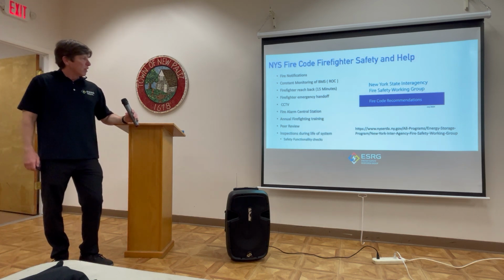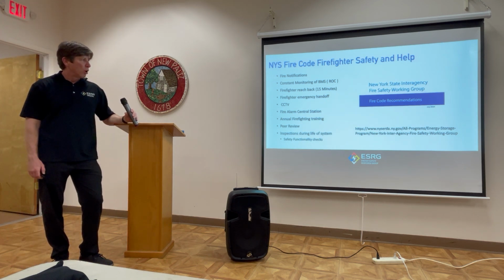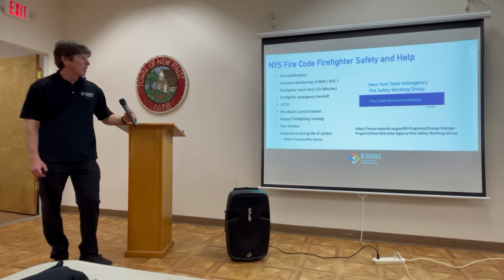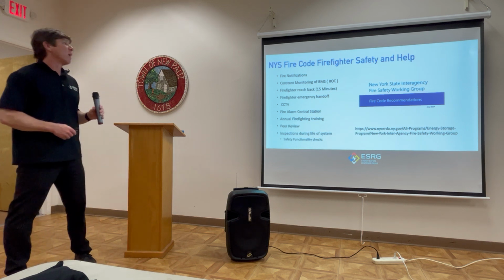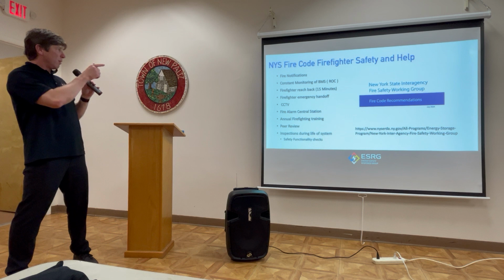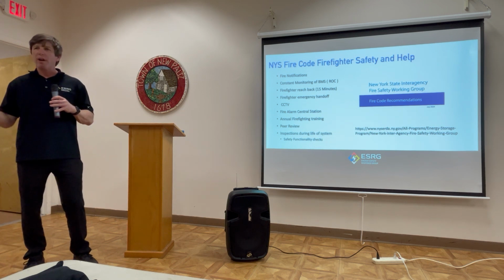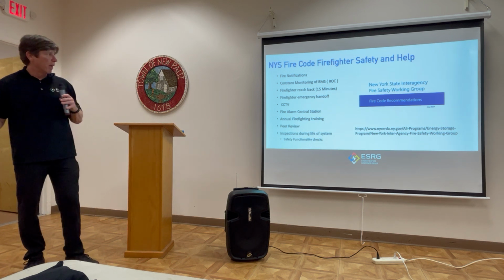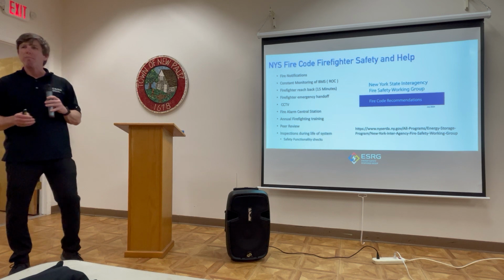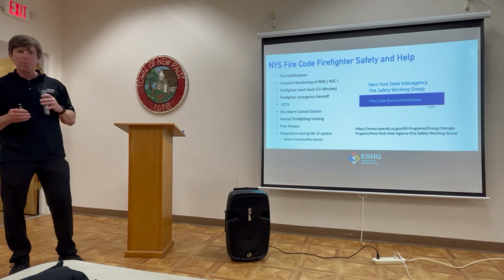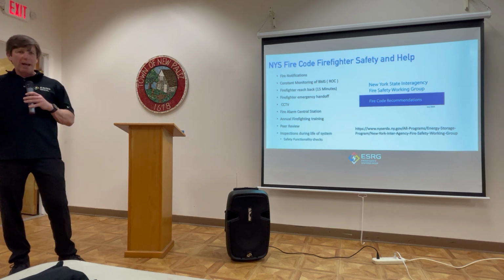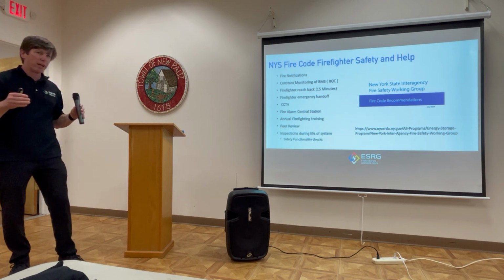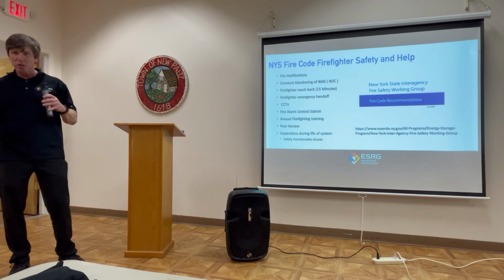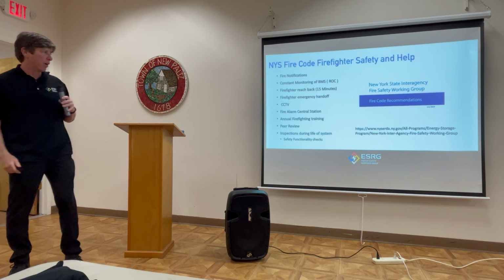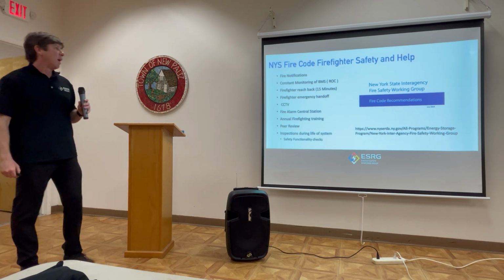Some of the things in the new 2025 code, which is now mandatory as of January 1st of this year: fire notifications, how do we notify the fire department when something happens, that's spelled out. Also the constant monitoring of the battery management system, it's remotely monitored by a remote operations center, and often it's also monitored by the manufacturer themselves. So if they install a Tesla system, the company that installed it monitors, and also Tesla monitors. So it's always being looked at.